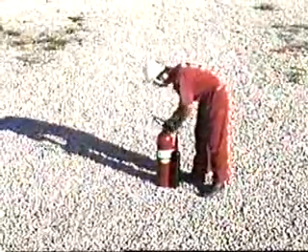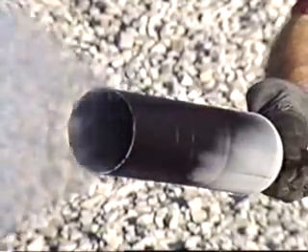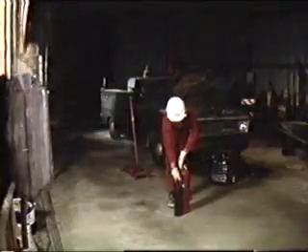To operate the large CO2 unit, remove the pin, hold the horn at its hand grip, aim at the fire, and squeeze the handle. It's very important to remember not to grab the horn while operating the extinguisher — CO2 extinguishers emit a frigid gas, so the horn gets very cold. For fires involving electrical equipment, aim to discharge directly at the flames. Continue discharging to assure the fire is out and to prevent reigniting. De-energize the equipment as soon as possible to eliminate the electrical hazard.